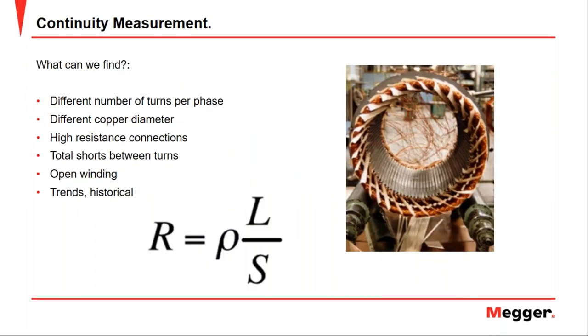What can we find? We know that the cable resistance is directly proportional to the length and inversely proportional to the diameter. So variation in the winding turns will result in variation in the motor resistance imbalance. Hence, we can detect the following problems.